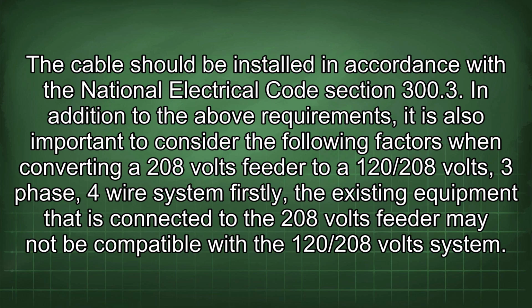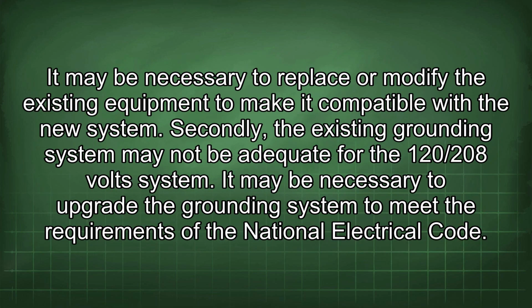In addition to the above requirements, it is also important to consider the following factors when converting a 208 volts feeder to a 120/208 volts 3-phase 4-wire system. Firstly, the existing equipment that is connected to the 208 volts feeder may not be compatible with the 120/208 volts system.